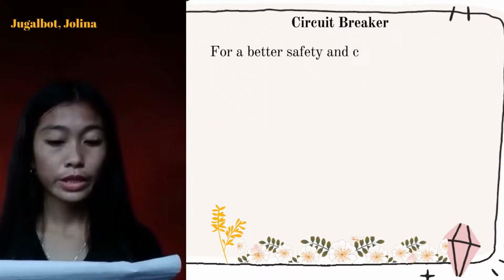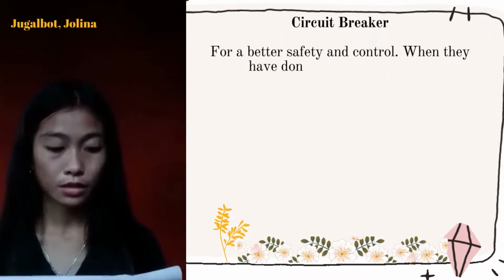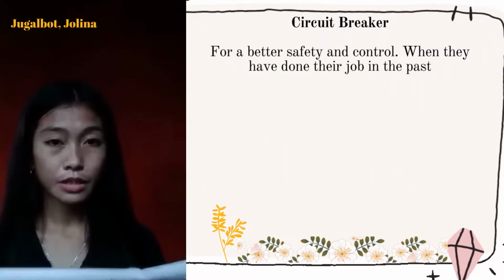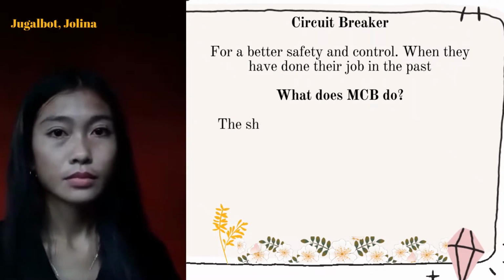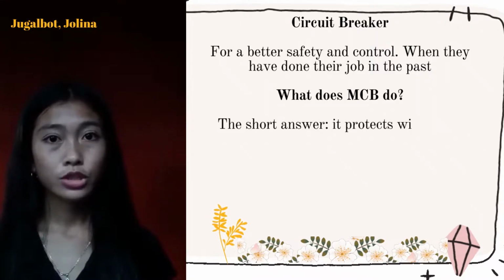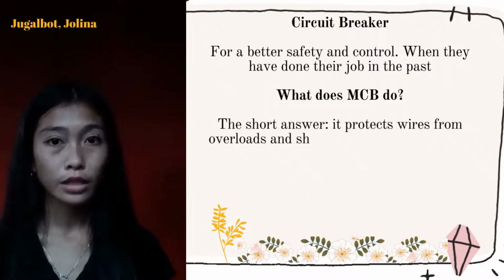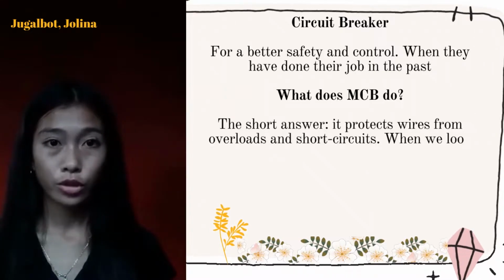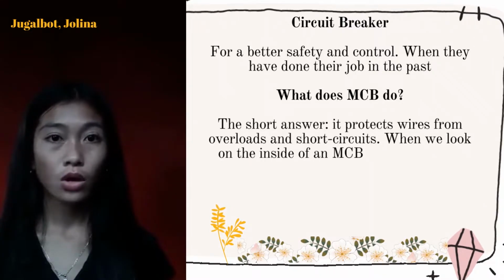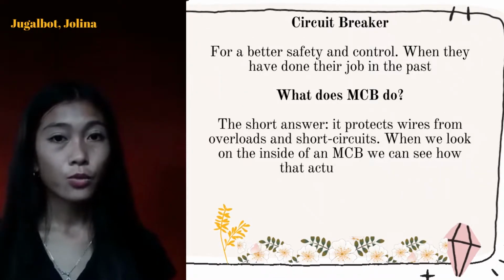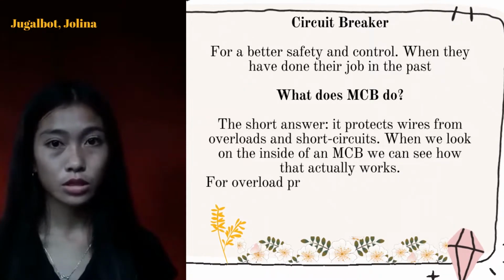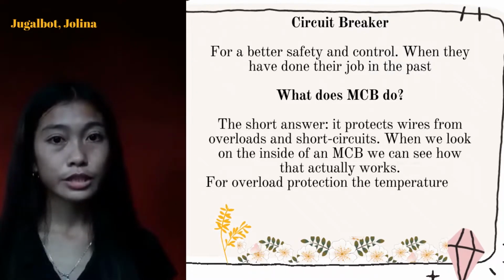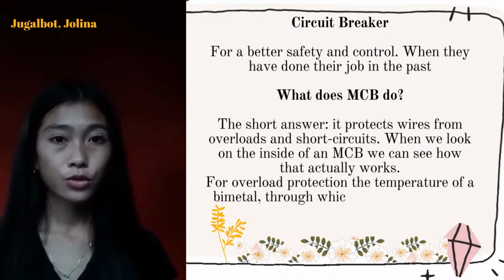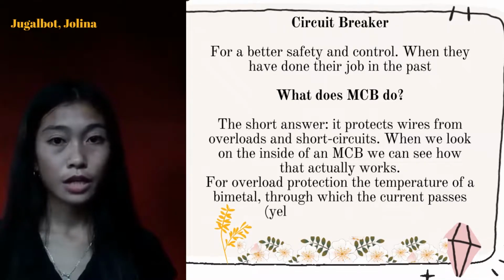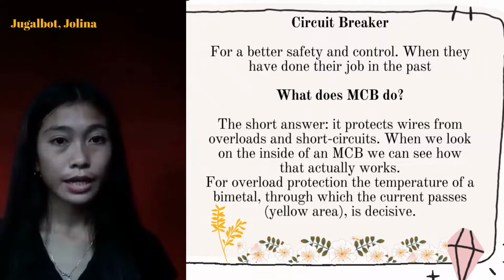Circuit breaker. For better safety and control when they have done their job in the past. So what does an MCB do? The short answer is, it protects wires from overloads and short circuits. When we look on the inside of an MCB, we can see how that actually works. For overload protection, the temperature of a bimetal through which the current passes, the yellow area, is decisive.